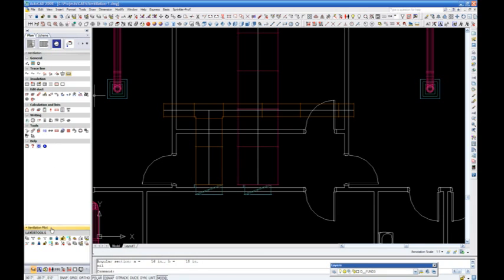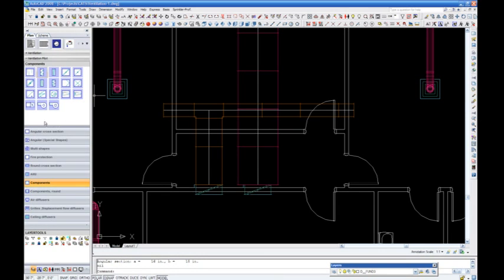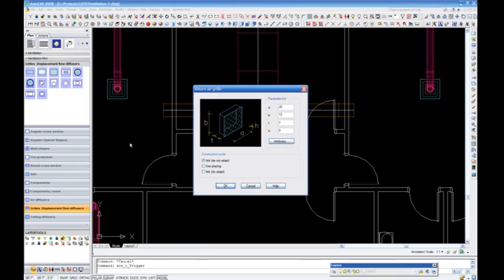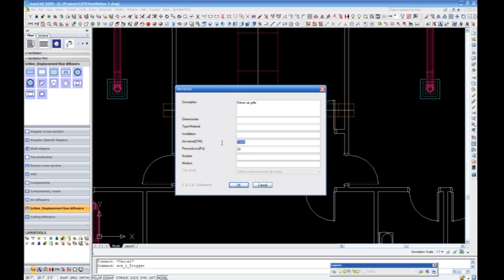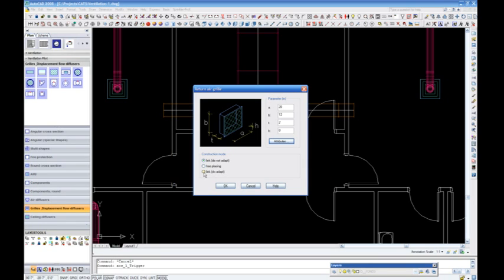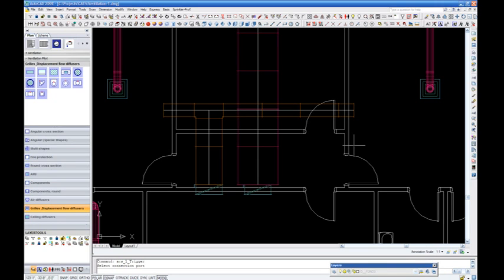In the C.A.T.S commander, we will now select a return air register for the duct opening. In attributes for the return air grill, we will revise the value to 1200 CFM. Select OK. You will then select the type of connection to connect the return duct. Select link, select OK. Select the end of the duct to place the return grill.